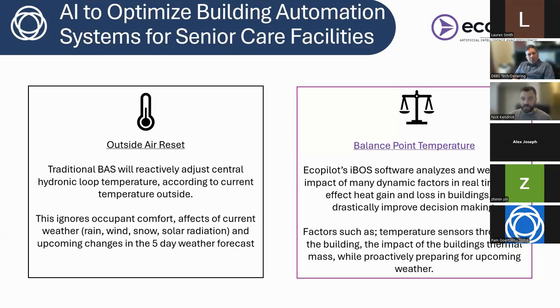So what our algorithm takes into account is components such as, as I mentioned, the weather and the internal comfort of the building, but additionally the thermal mass of a building. We plug in an assumption at the start of a project, where we come up with a calculation of how much the building materials' thermal mass is going to affect the amount of heat energy coming in and out of the building, and factor that into our decision making. If you have a building that's got a high thermal mass, meaning concrete, brick, stone, every building already does this naturally, we're just taking advantage of it. A thermally heavy building with those heavy building materials is going to change temperature slower than, say, a stick frame building, just steel and glass. Those kinds of materials don't absorb that heat and release it slowly.